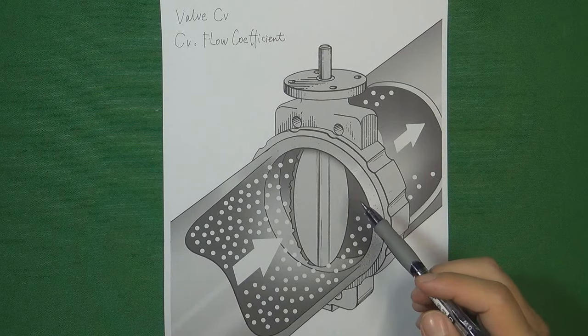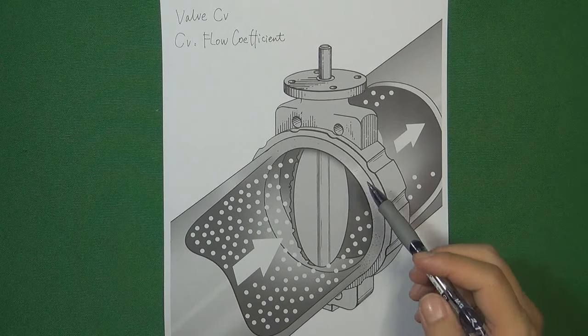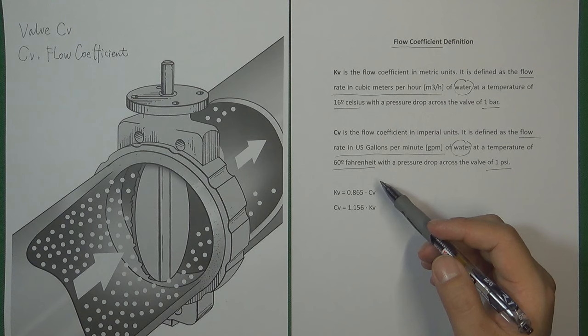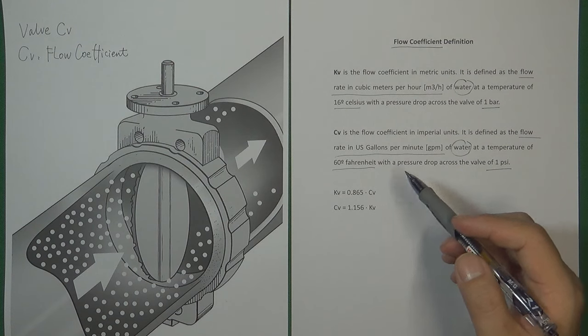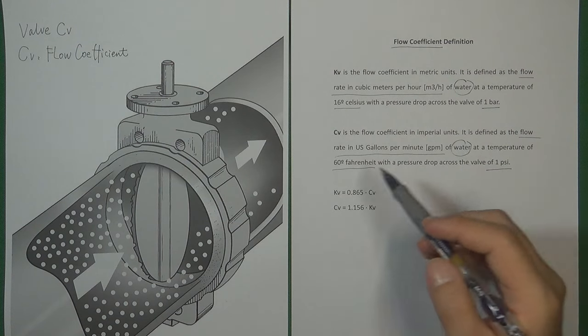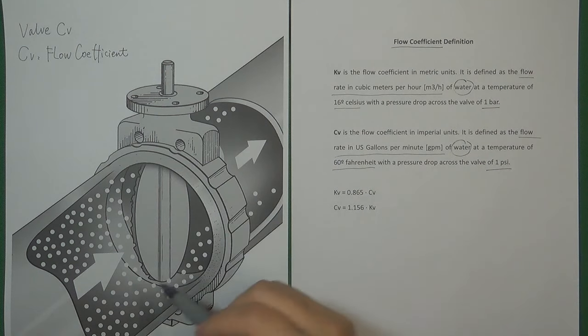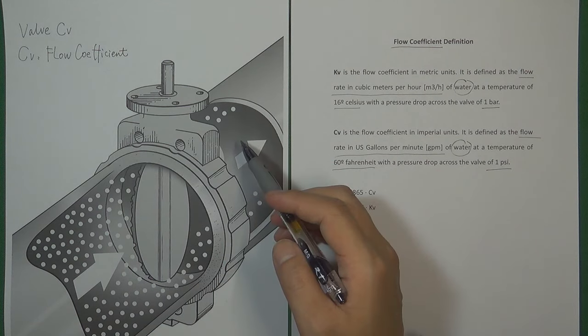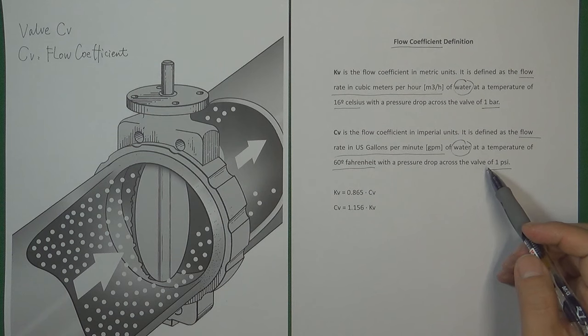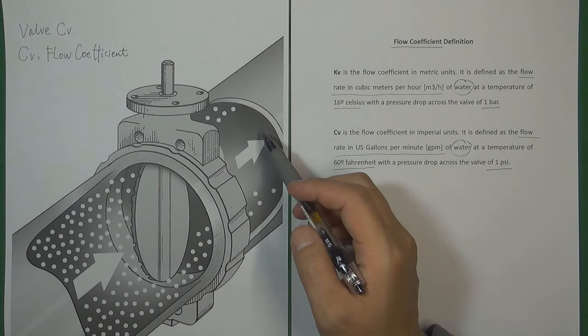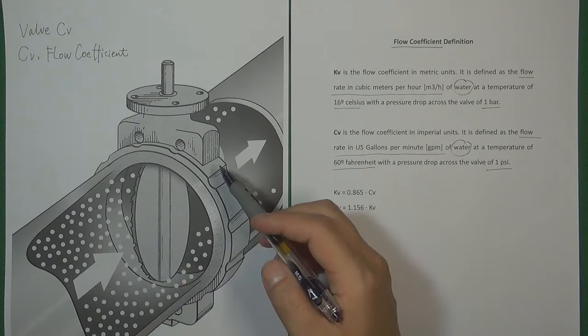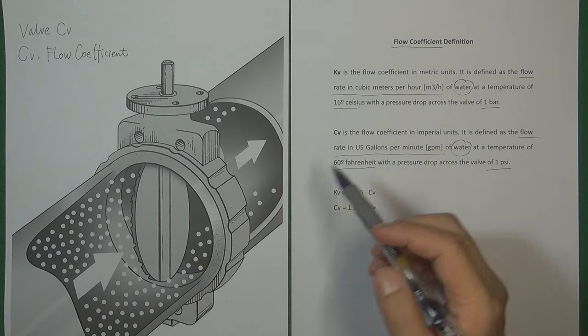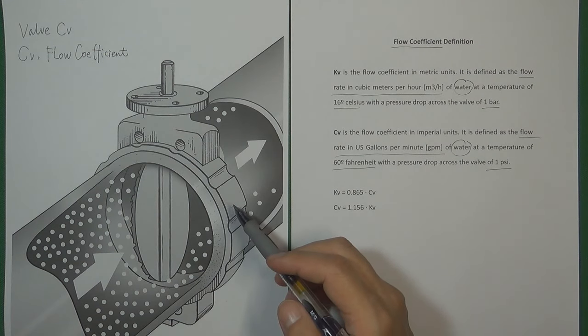Let's look at how to test a valve to get the correct valve CV. The basic principles for valve CV testing are easy to understand. We are going to use water at 60 degrees Fahrenheit as the testing medium. Then we push the water from one side to another using one psi of pressure. Then we calculate how much water transfers through the valve. For example, if in one minute 10 gallons of water transfer through the valve, then this valve's CV is 10.